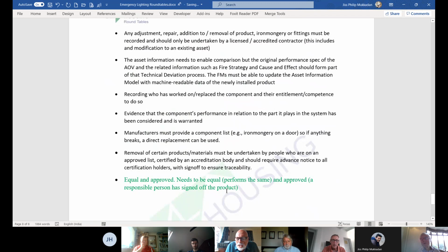I mean, typically they're done either from spacing tables, which are relatively easy and anyone could do, or from a computer design of the whole lighting installation. And that requires a fair bit more skill to be able to do. But in either case, you would be able to replace a component and check that the performance was not eroded by the change, the substitution you've done.